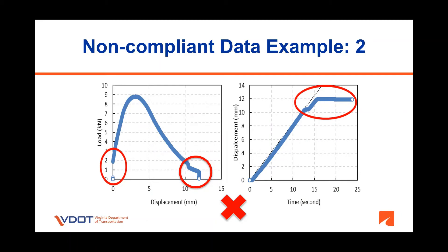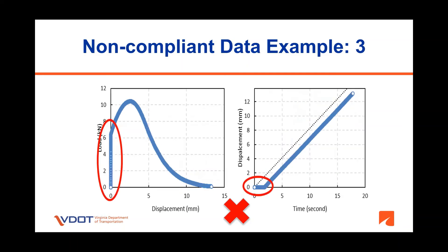Another example of non-compliant data. In this case, a seating load was applied at the beginning of the test and there is an LVDT error towards the end of the test. The test software should be configured to remove the seating load, and the LVDT installation and range should be checked. In these figures, it seems that the loading RAM and LVDT are not synchronized, therefore resulting in non-compliant data and inaccurate CT index values.